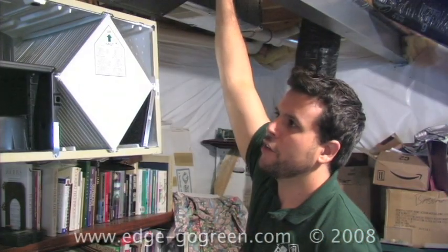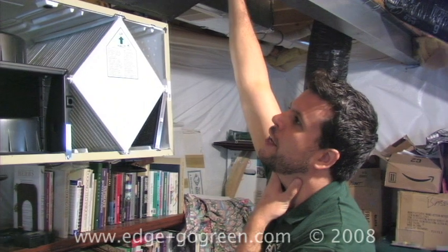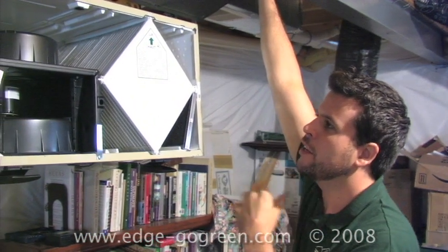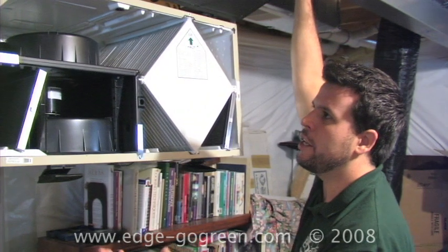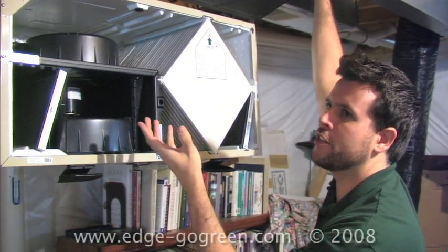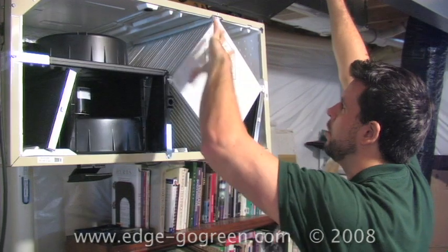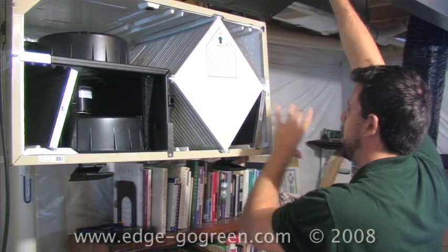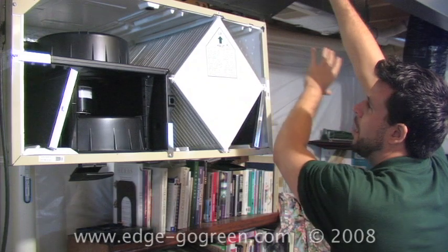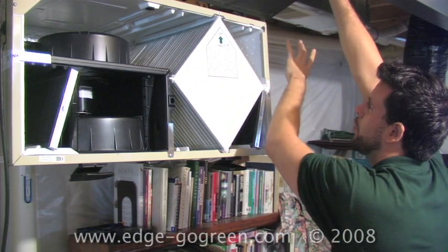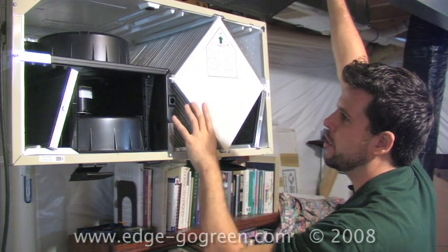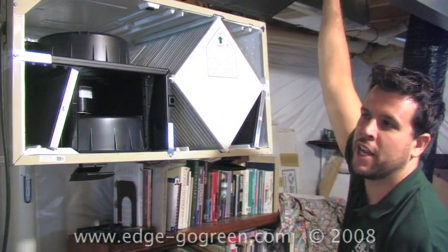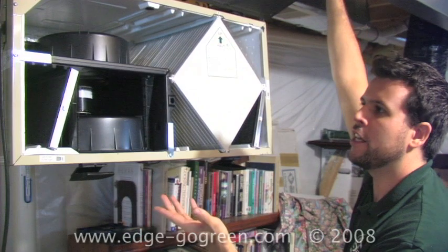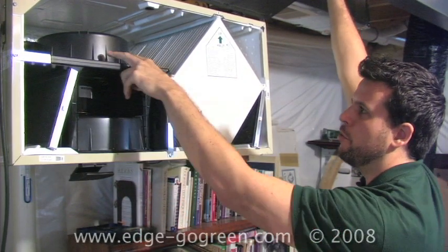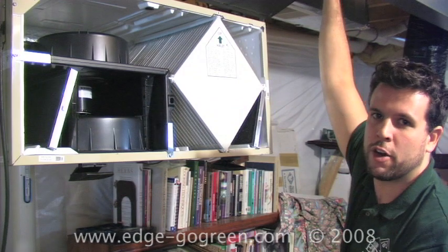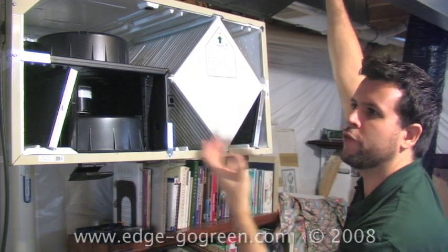So here's the inside of our ERV unit. We've got the casing opened up so that we can look at its inner workings. Basically what happens inside of an ERV is that you're pulling stale or exhaust air outside of the home. It's moving through one channel, in the top, down through the heat exchanger, and out through an exhaust supply. You're bringing in outside, or what we would call fresh, air, which comes down the other side of the heat exchanger and then moves in a supply duct that goes back into the HVAC system. The net effect of the ERV is that you've got a balance with two equal-sized fans, top and bottom here, of airflow for both pulling air out of the house and bringing fresh air in.